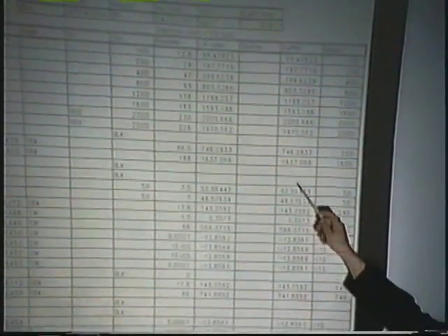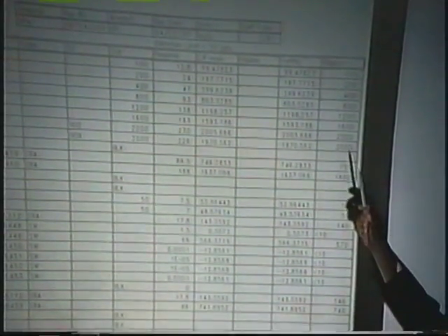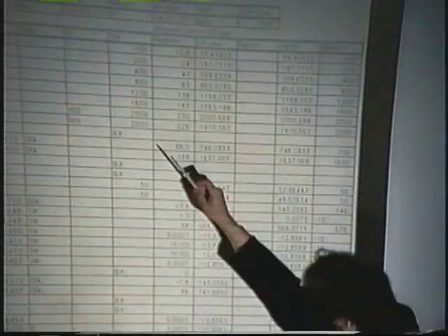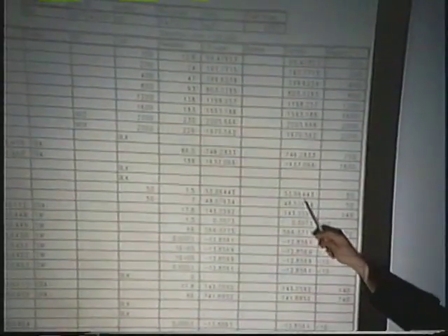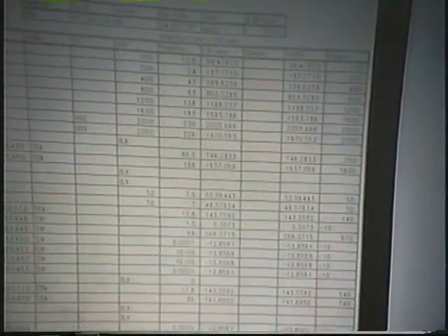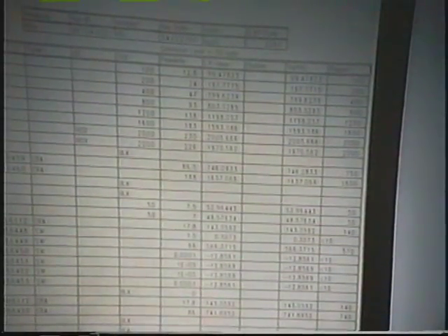But you can see that even though we've got 52.9, when we took what we knew was 100, we got back actually 99.5. In the case of what we knew was a 2000, we got back 2006. So 52.9, or 53 actually, as far as how we would express that to our customer in describing a sample, is 50. And in these, they tend to round to tens, in the tens and hundreds places. And that kind of takes care of the error.